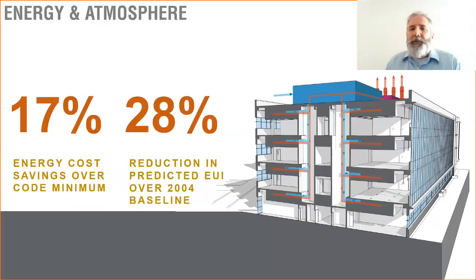The energy and atmosphere credits: labs are also really energy hogs. The primary reason for that is the chemical use in a science lab building. All of the supply air has to come in 100% from the exterior. It cannot be recirculated or refiltered and reused. So the air handling units pull in 100% of the outside air, and it has to be either heated or cooled and distributed in the building. Also because of the chemical use, 100% of the exhaust air has to be gathered in return ductwork and exhausted. Working with our mechanical engineers, we were able to select systems that targeted this energy use and targeted energy savings. So we were able to save about 17% over the code minimum at the time, and 28% of the baseline EUI, which is the energy use intensity.